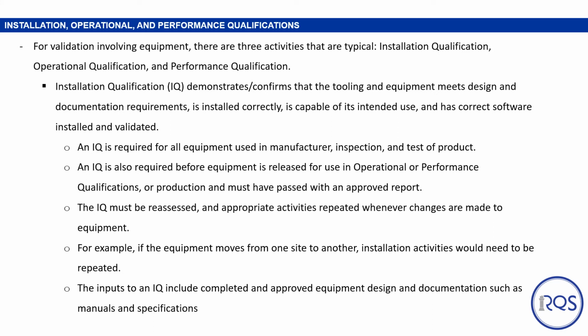For validation involving equipment, there are three activities that are typical: installation qualification, operational qualification, and performance qualification. Installation qualification, or IQ, demonstrates that the tooling and equipment meets design and documentation requirements, is installed correctly, is capable of its intended use, and has the correct software installed and validated. An IQ is required for all equipment used in manufacturing, inspection, and testing of product, and is also required before equipment is released for use in operational or performance qualifications or production, and must have an approved report. The IQ must be reassessed and appropriate activities repeated whenever changes are made to the equipment. For example, if equipment moves from one site to another, installation activities would need to be repeated.